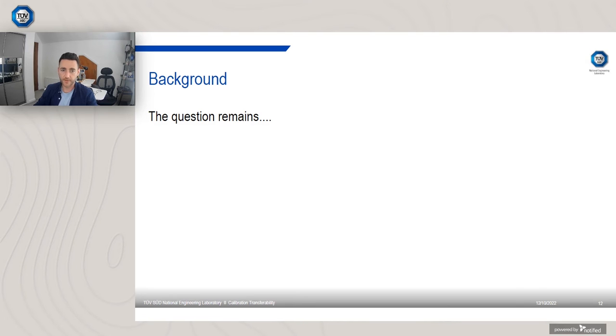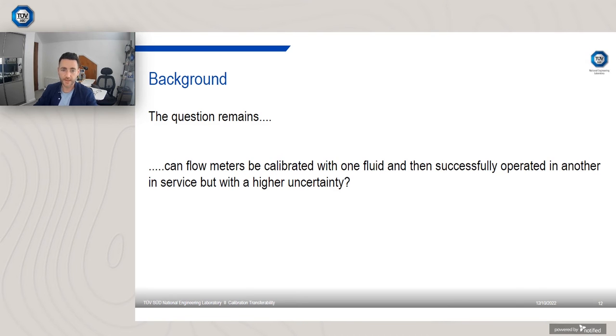So that's the background. The question still remains, however, can flow meters be calibrated with one fluid and then successfully operated in service with a higher uncertainty? So yes, there's no reason why you couldn't calibrate a flow meter in one fluid and use it in another, but certainly straight away it'll have a higher uncertainty. And crucially, what is that uncertainty? How do we know, and how will we know eventually? What steps have to be taken for industry to be aware of what the uncertainty would be if you calibrate in one fluid and then use it in a completely different fluid?